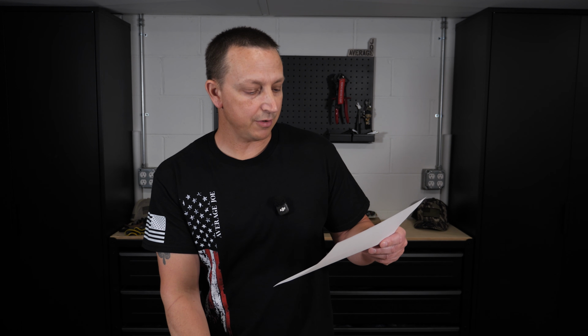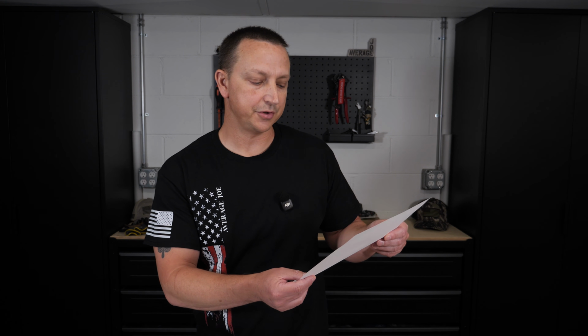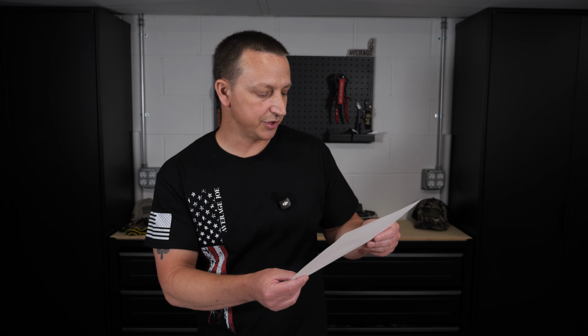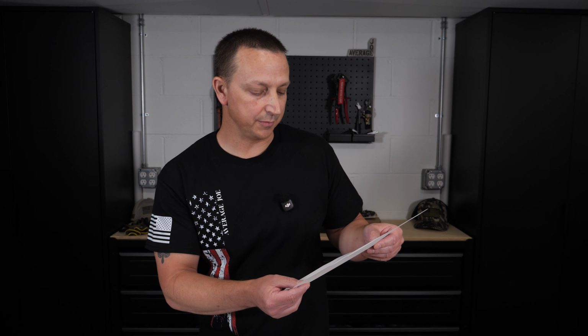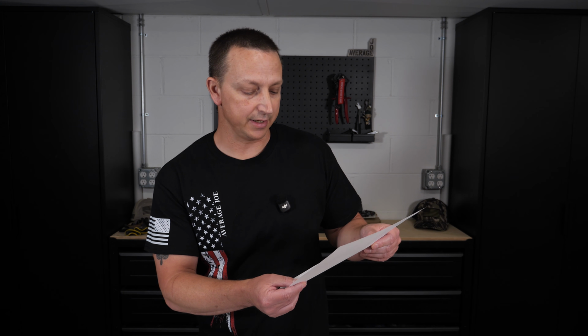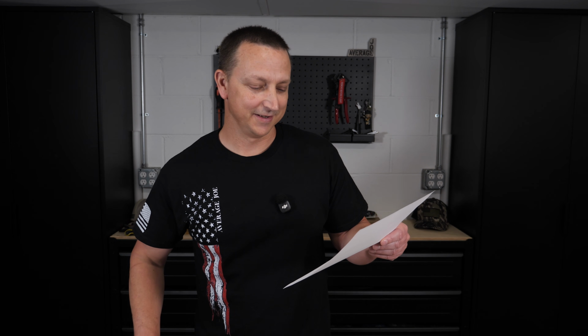After reviewing the video, our engineering team discussed the issue internally and provided a few additional recommendations for you to check. Step number 1, the ADS dip switch address is the communication address for each battery. So the addresses cannot be the same between batteries. So that is opposite of what they said in the first video. Step number 2, communication between the battery and inverter uses RS-485 communication. Opposite of what they said in the other one.